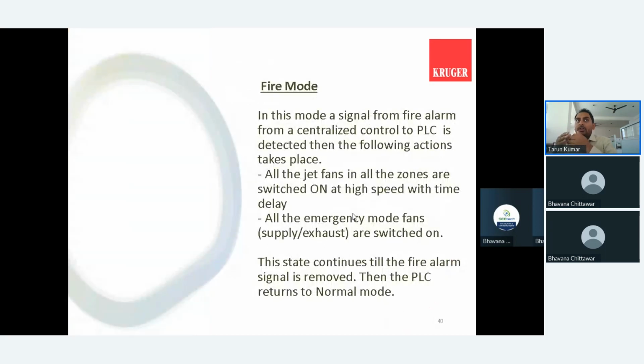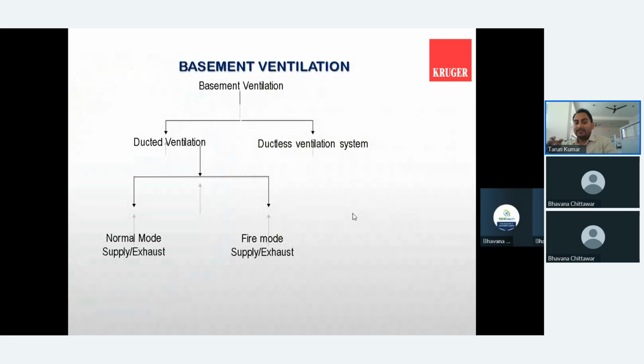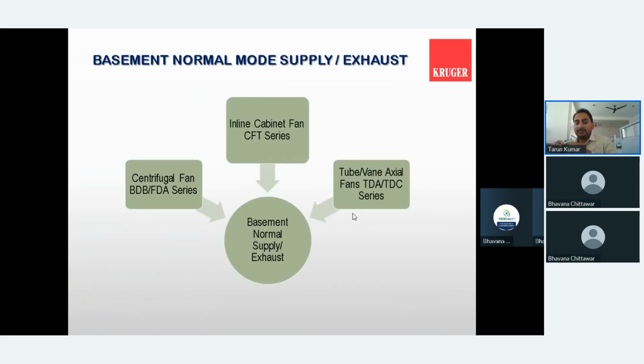Then it comes to the fire mode. When some fire happens there and your ppm level increases to more than 25 ppm, the PLC panel will sense it. There is logic for the temperature sensor also. When the temperature also increases, the CO sensor and temperature sensor will give the signal to the starter panel, and the starter panel will give the signal to the jet fan, and in that case the jet fan starts running at high speed. You can say it is an emergency mode. In emergency mode, all the fans, the axial fans as well as the jet fans, will start at high RPM, high speed, and will try to evacuate whatever smoke or fumes are there in the basement.